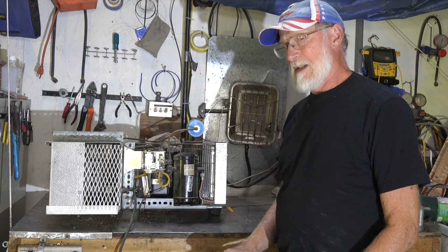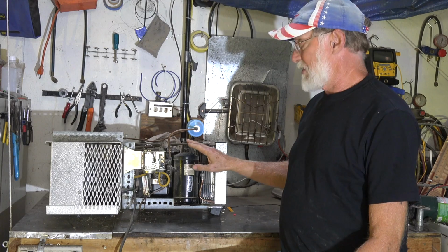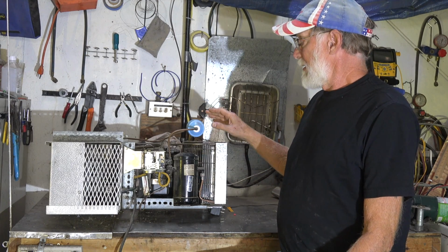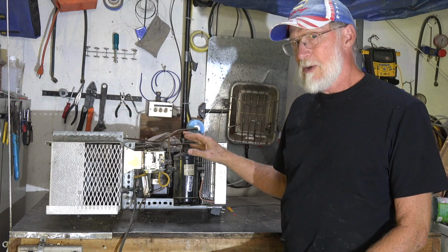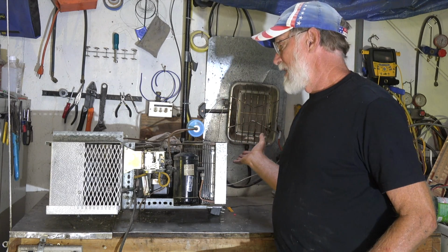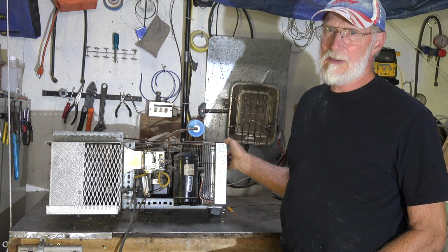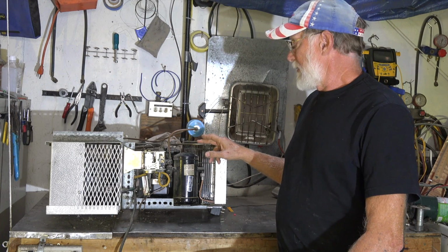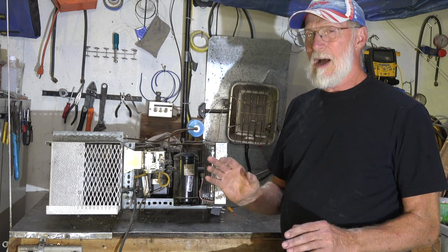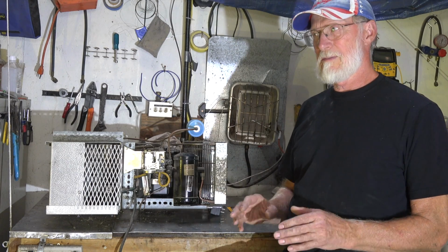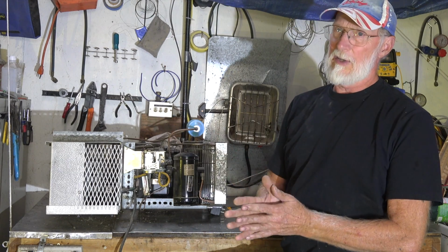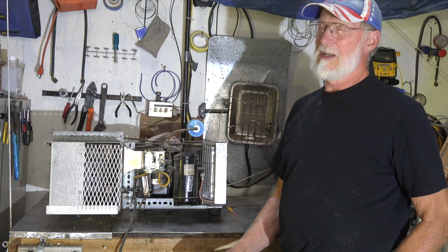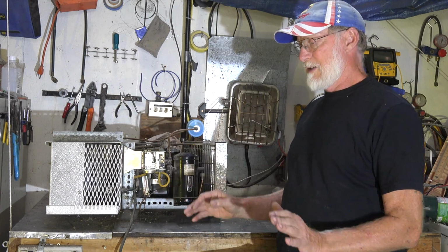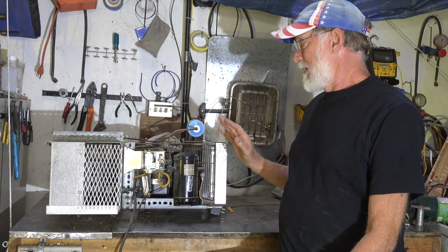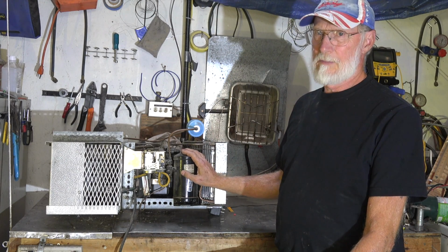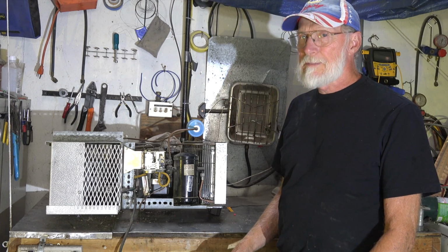Well, why do we have it? The reason for this thing is pretty simple. Refrigeration systems, and this is like a 40 degree box, operate at varying loads, some pretty spectacularly variant. Let's say I've got a lot of product that I brought into my walk-in cooler. The load on this is going to go way up. That means it needs more refrigerant.